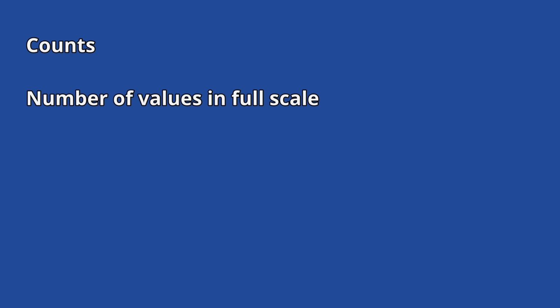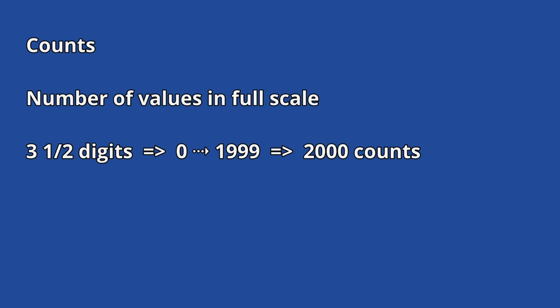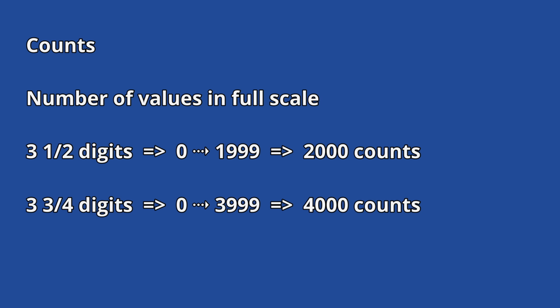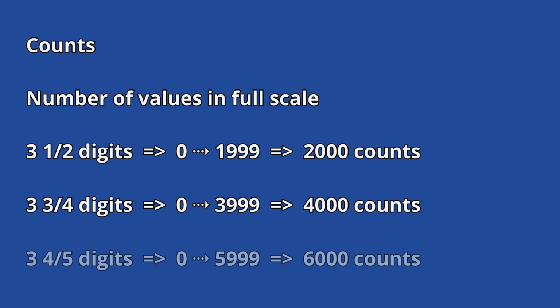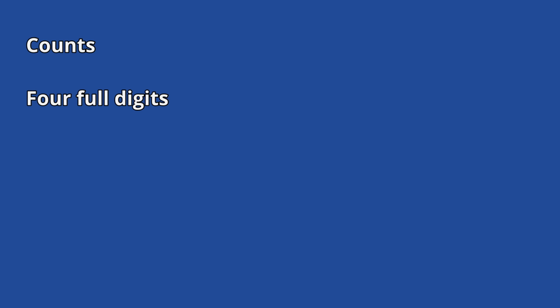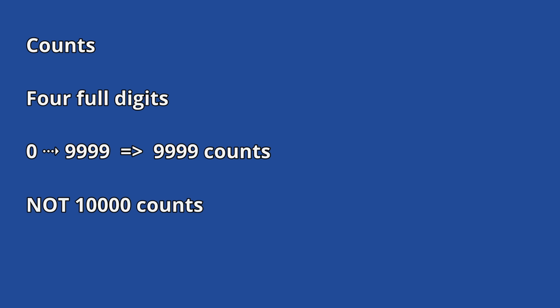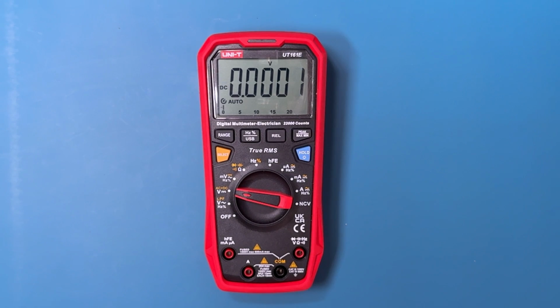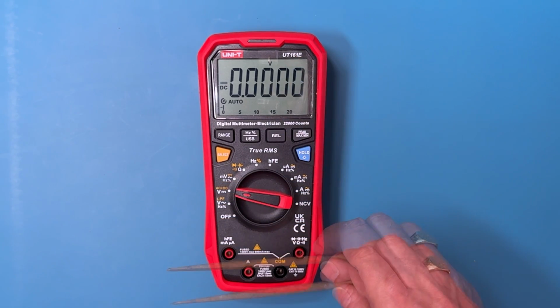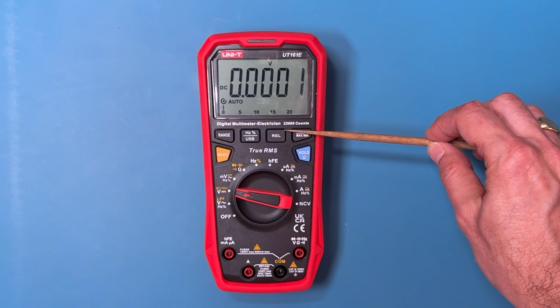Counts was introduced as newer terminology to describe the number of values in the full scale. Thus, 3.5 digits is 2,000 counts, a range that runs to 3,999 is 4,000 counts, 5,999 is 6,000 counts. The oddity in naming has a small twist at the edge where 4 full digits are used. These are referred to as 9,999 count meters rather than 10,000 count meters. I suspect this is because consumers might expect to see 5 digits in 10,000 count meters instead of 4. Benchtop multimeters continue to be marketed in terms of digits, while handheld units, like this UNI-T, are specified in terms of counts. We can see the 22,000 counts shown here.